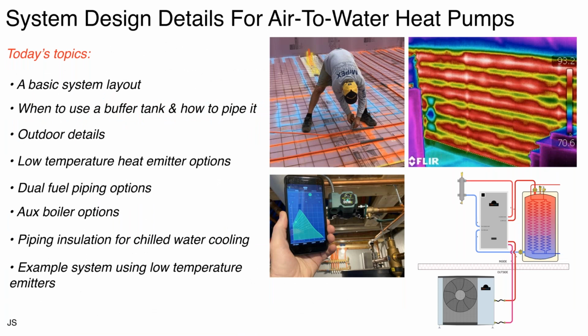What we're going to talk about today is, as Tim was saying, we're going to dive into some of the nuts and bolts. We're going to look at a basic system layout where we're providing space heating, cooling, and domestic hot water. Then we're going to look at buffer tanks, which can be piped up in different configurations. We're going to show you 3 different configurations and talk about the strengths and limitations of those. We're going to talk a little bit about the outdoor details, basically getting this unit up above snow and keeping it away from pollutants or sources of vapor that are just going to load up the coil in cold weather. And then we're going to look at low temperature heat emitter options.